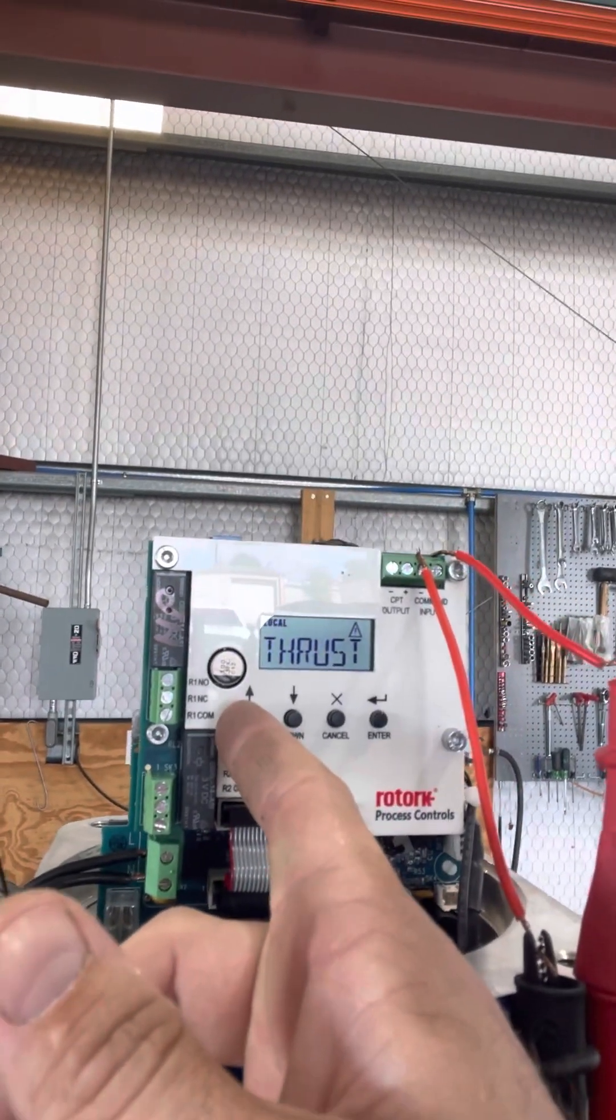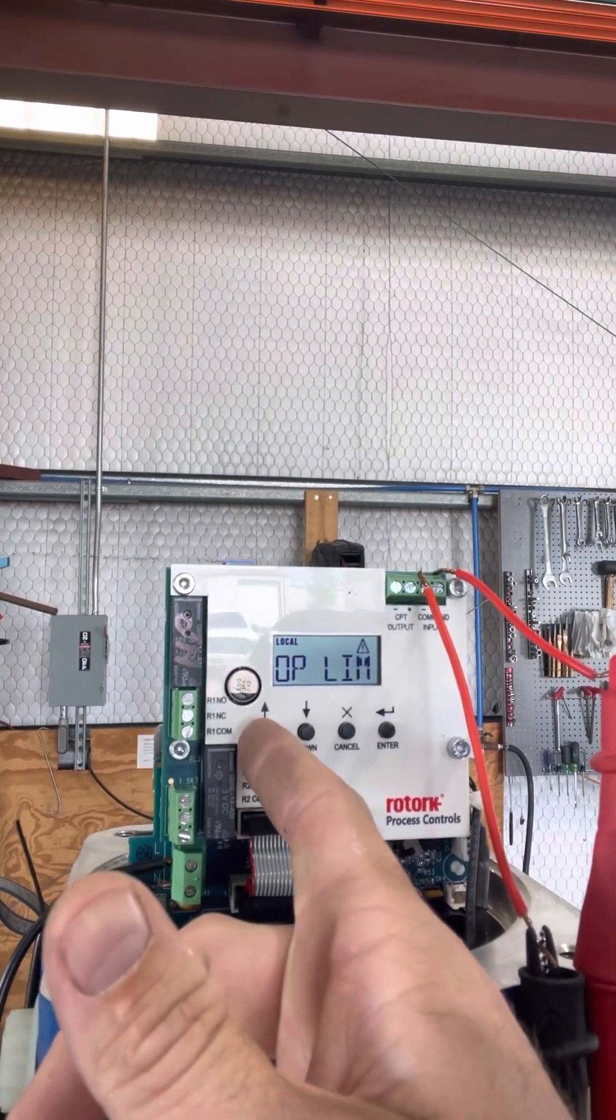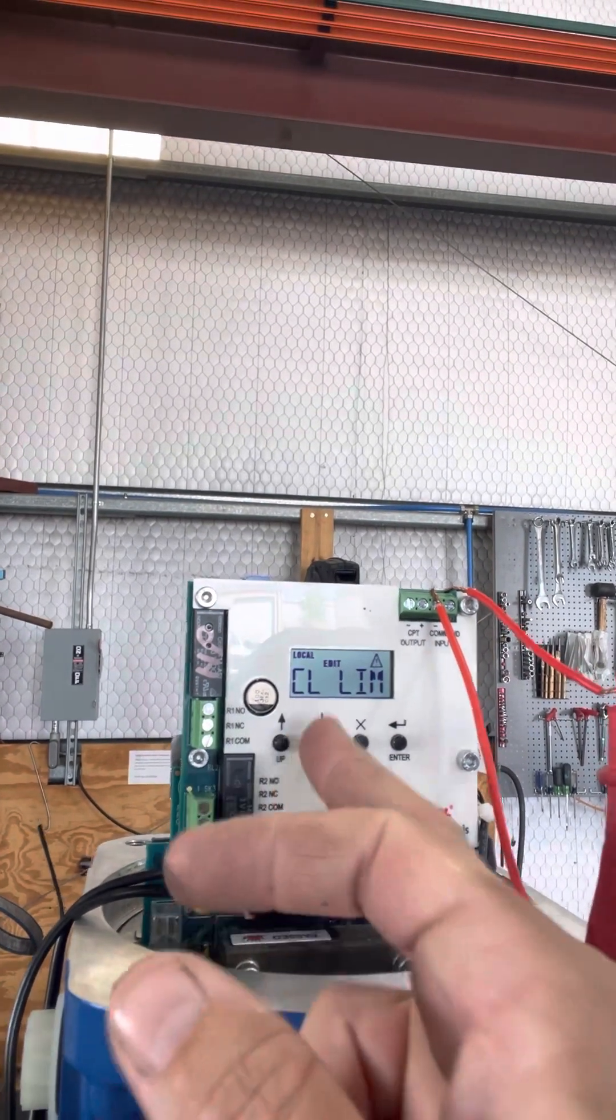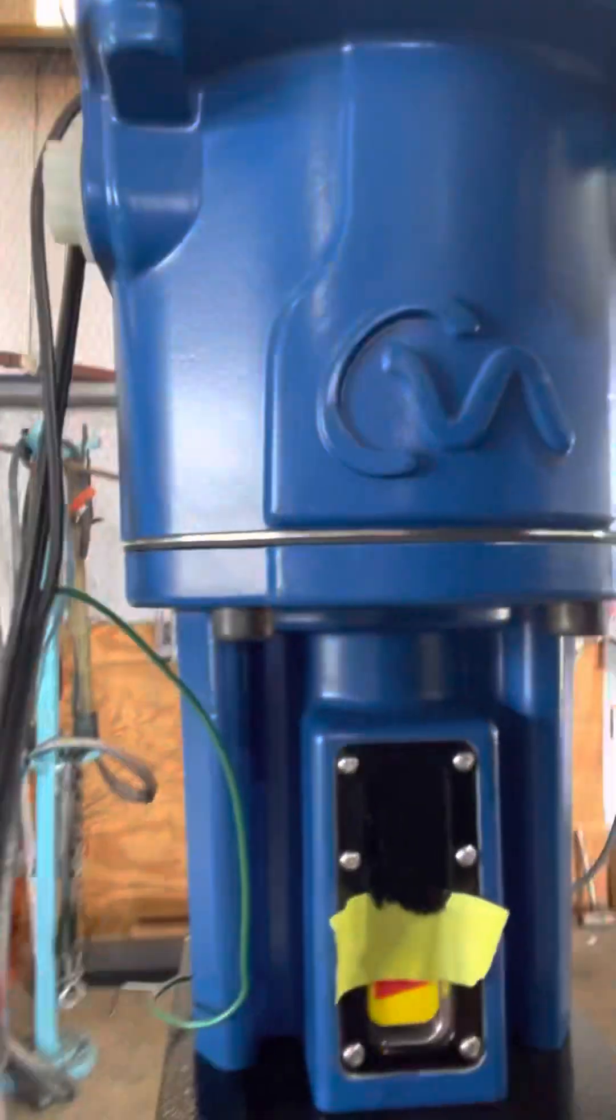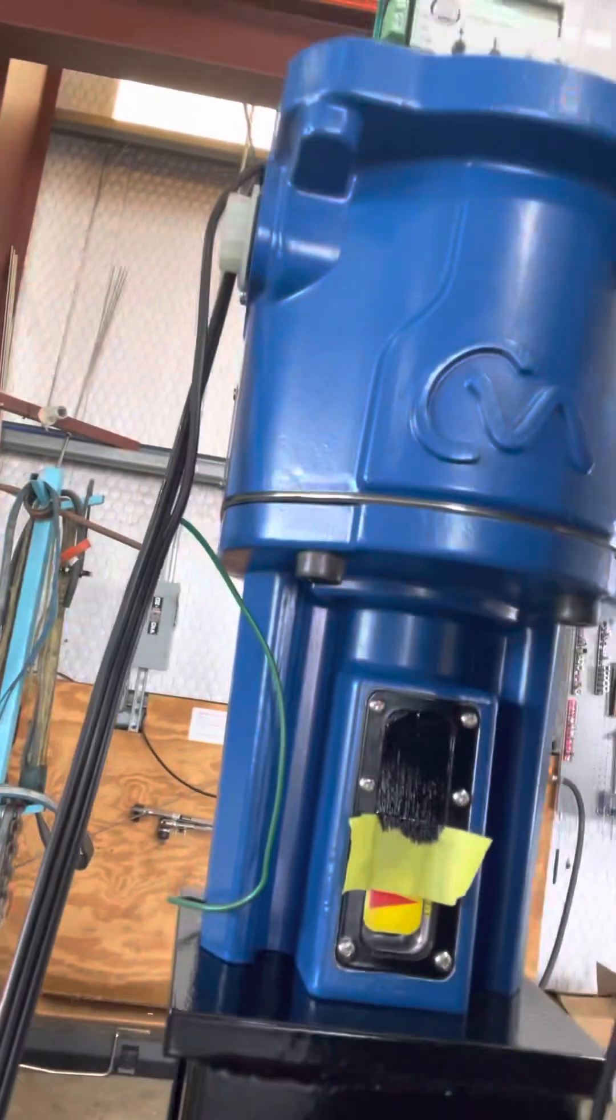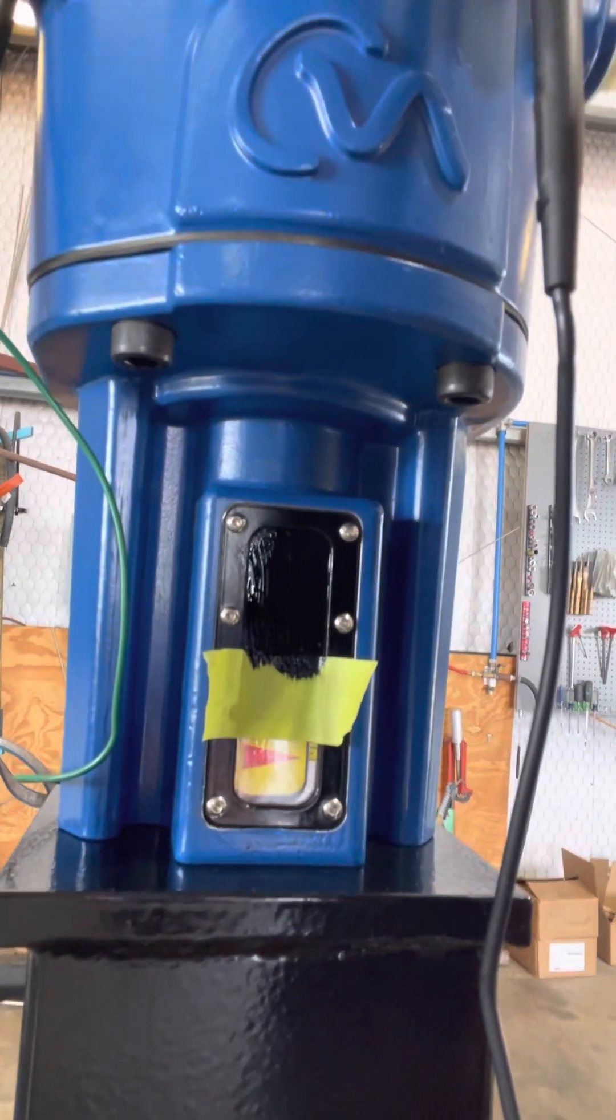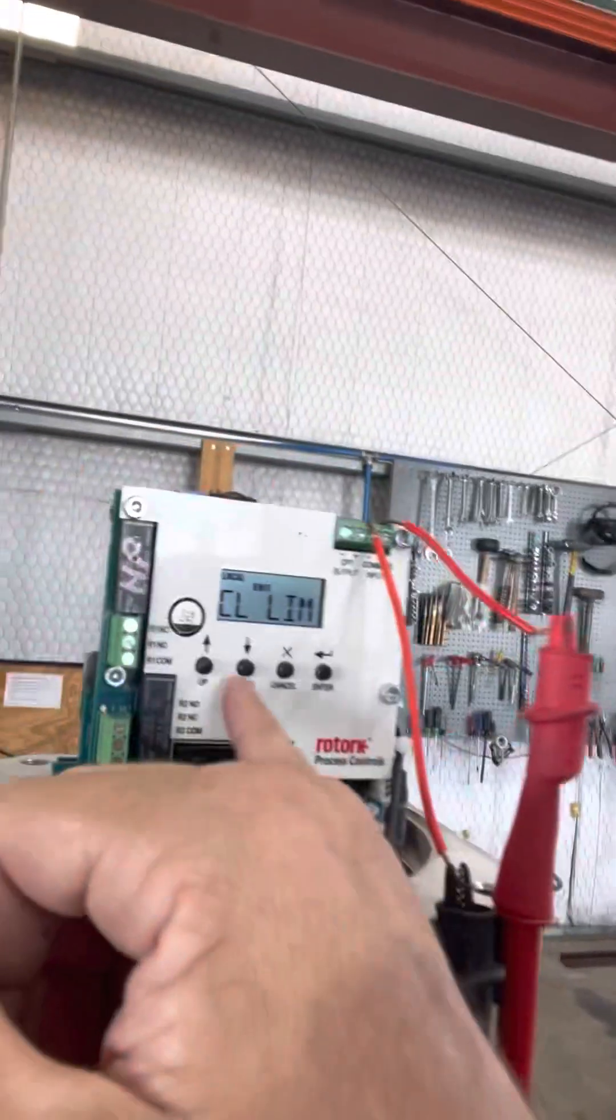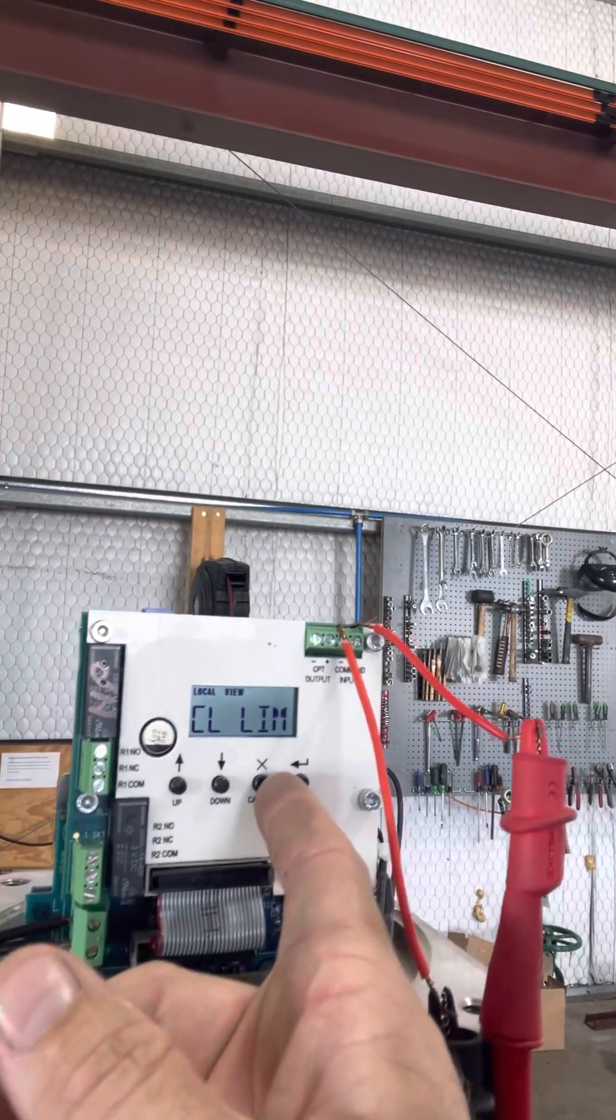So now you're in local remote. You got to hit exit or the cancel button to cancel and be able to go through the menu. So what we're going to do here is we're going to set our closed limit. Now you would hit enter, enter, go to edit. Now you can press the up button, it travels up. Down button travels down. Behind this, we taped it off because we're painting it. There's a travel scale, you can kind of see it there at the bottom. So you can see right there, I stroked it to the closed position. So now that we're in the closed position, we hit enter, saved. Now we back out of that and hit back again.